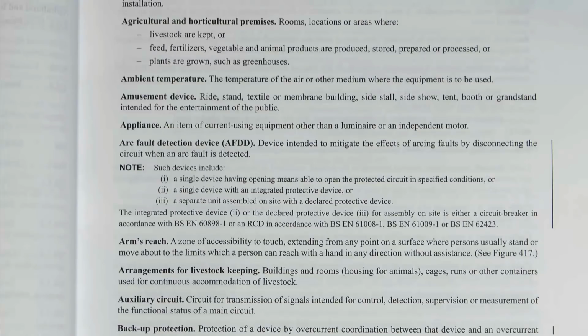The third type, you can actually buy these as a separate unit assembled on site. So you'd buy a circuit breaker, and there's a separate arc fault detection device which you can clip onto the side or attach in some fashion, so it effectively becomes the combined device type.